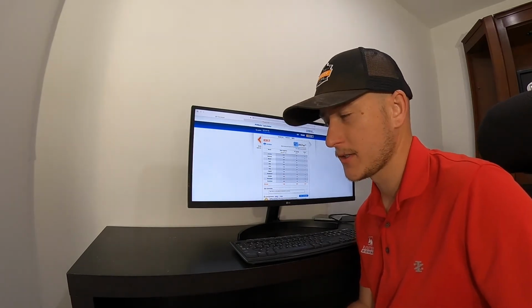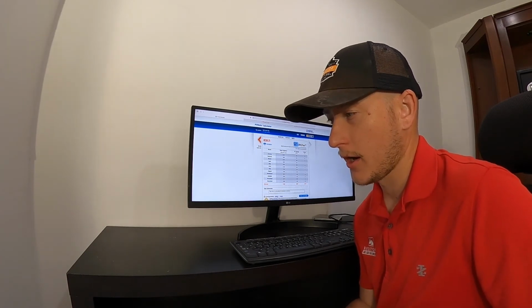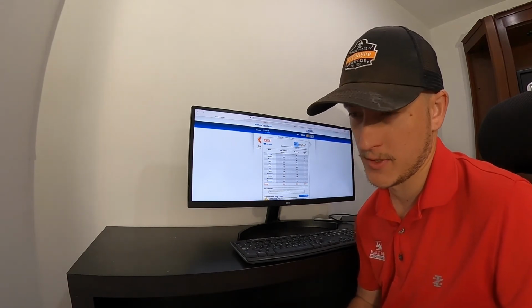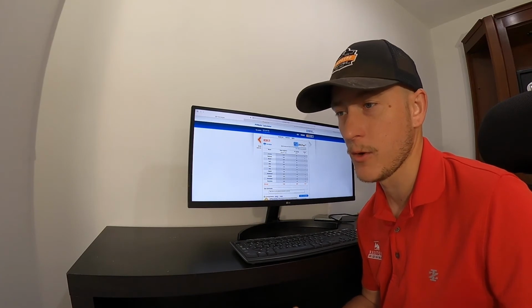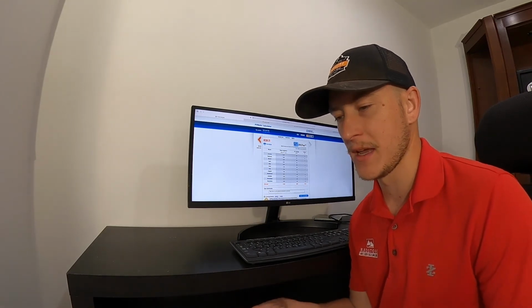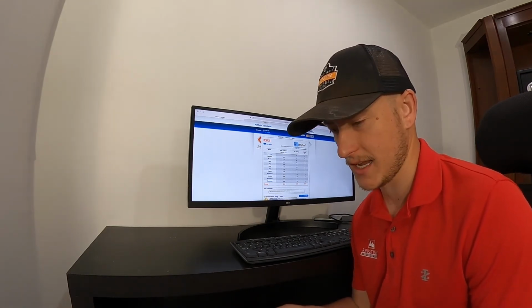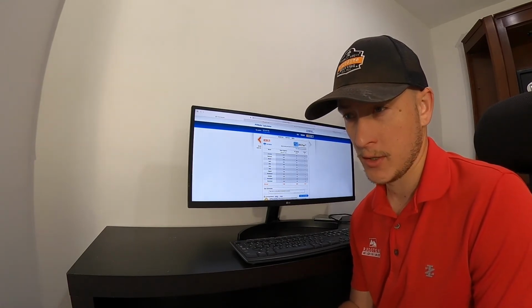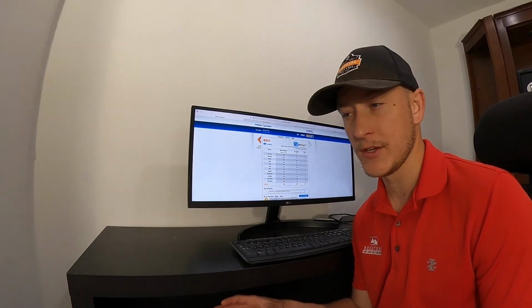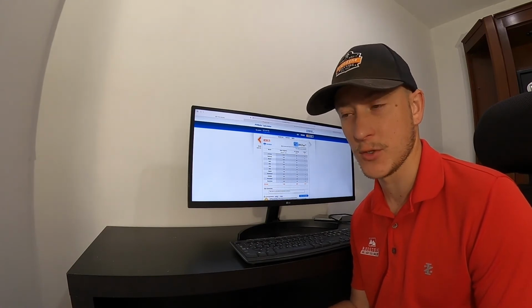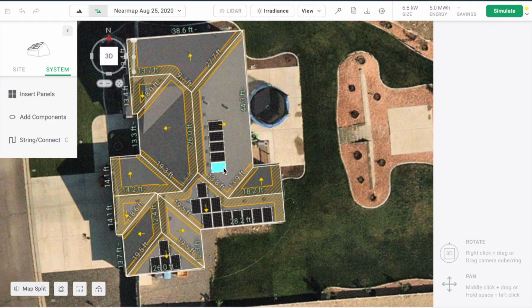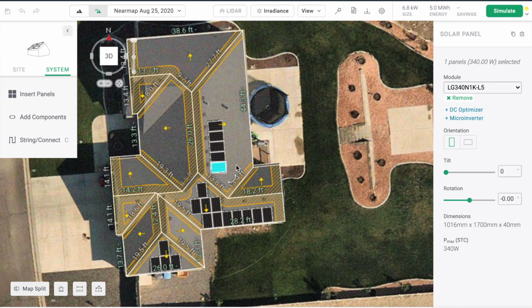Another thing that you may want to consider is the cost of adding one panel versus the cost of adding 2 or 3 or 4 or 5. There's going to be an amount that makes the most sense. On this solar installation, we had 20 panels. Each circuit could handle up to 15 solar panels. We had a circuit of 12, where we added those 3 panels landscape. And then we had a circuit of 8 where we added 7 more panels. And so we had 2 circuits of 15. Right there, we're kind of maxing out the system.